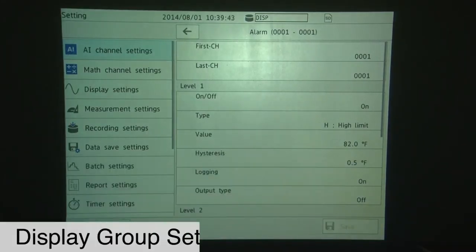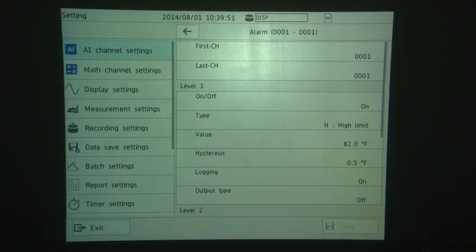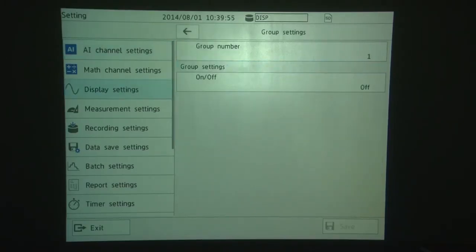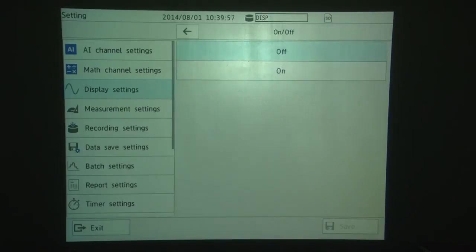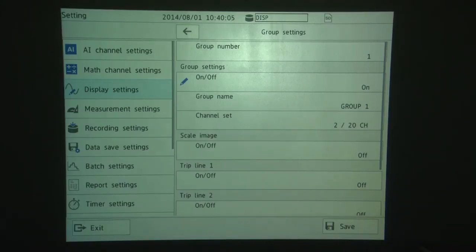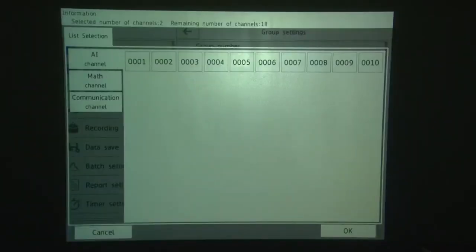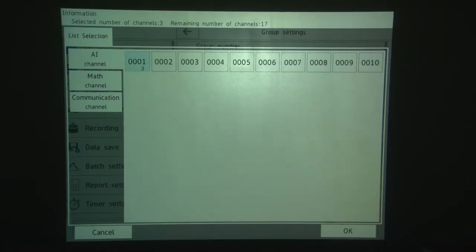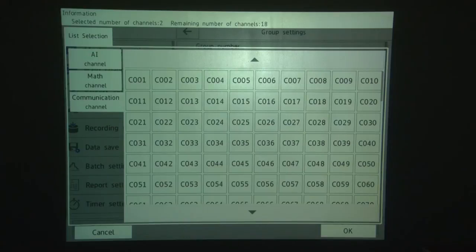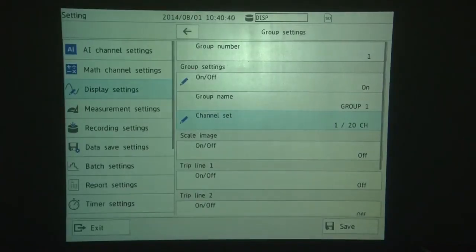The next thing we're going to do is visit the Display Group Settings and make sure we have Channel 1 in our Display Group so we can see it in Group 1. Go to Display Settings, touch Group Settings, turn on Group 1, and then you'll see a Channel Set selection. You can also assign a name to the group, and the default is Group 1. You can change that to any descriptive name you'd like to use. So for Channel Setting, we're going to touch Channel Set, and we're going to put AI Channel Number 1 all by itself in the group. And we're going to look at the other communication channel settings here, and we're going to turn off that channel. And Math Channel A001 we're going to turn off also because I want Channel 1 all by itself. And when you're done, touch OK. Now click Save.